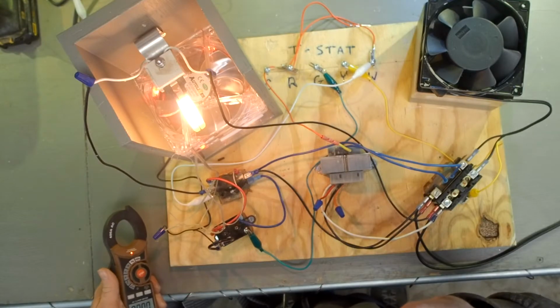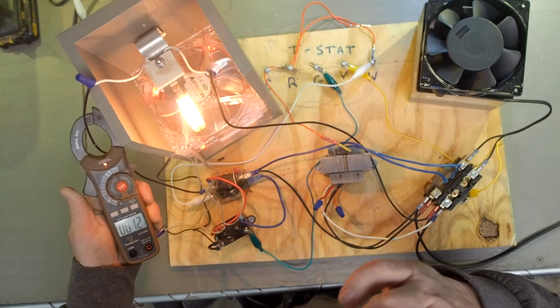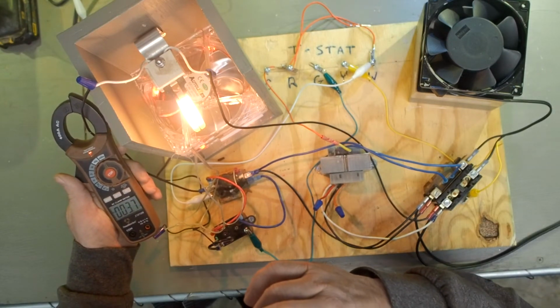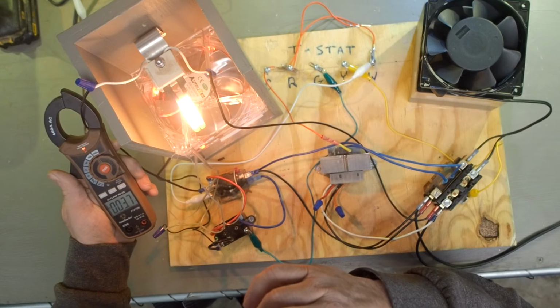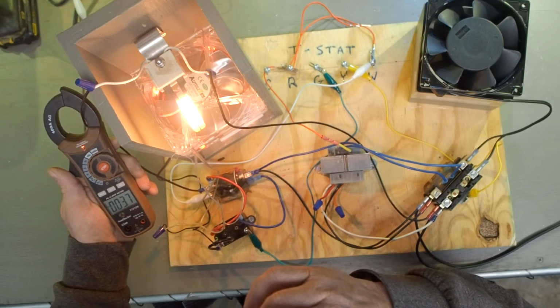One of the things that I thought was worth mentioning was that the hot surface igniter is pulling nearly 4 amps, which is about a fifth of what a 5 kilowatt element would pull.